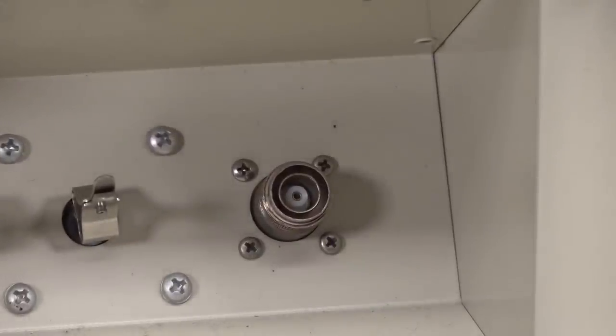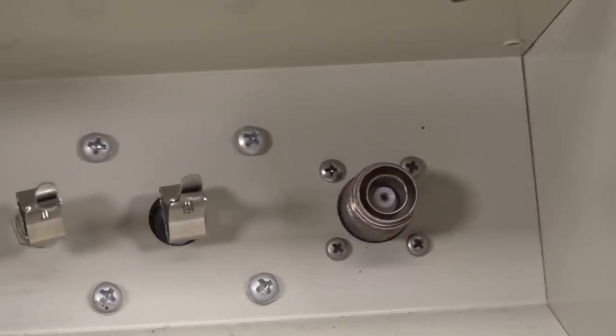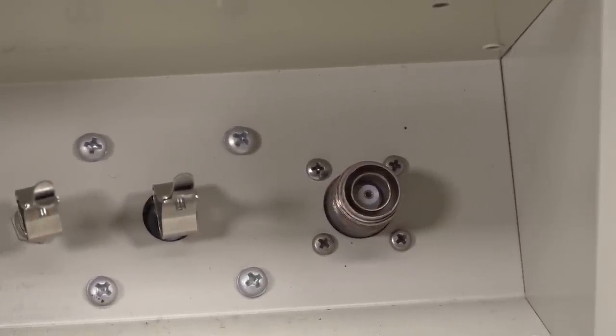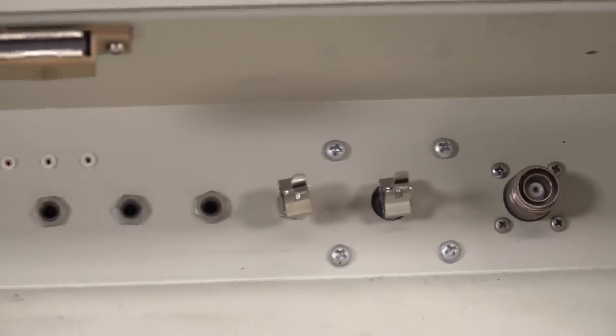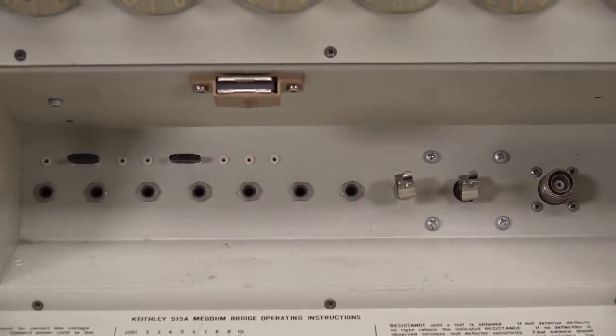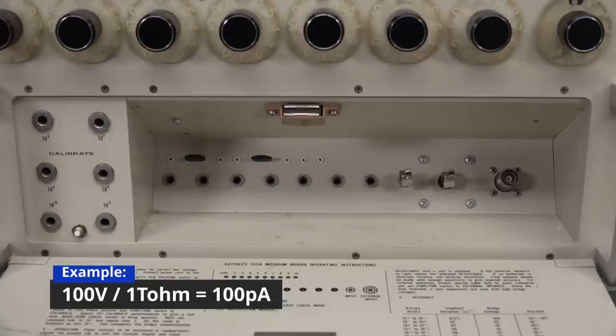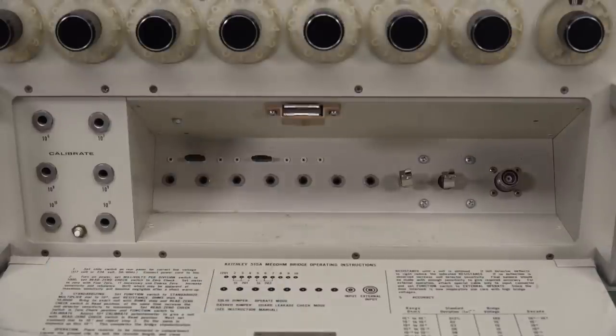And if you've seen my video, I'll link it in. If you haven't seen it, it's really good on the Keithley electrometer and how triaxial connectors work and how the art of measuring extremely low currents works. And that's what you need for something like this. You really need the shielded box triaxial connectors, which have ground and guard connections in there as well. Because when you're dealing with extremely large resistors like gigaohms and teraohms, then you need a really properly shielded and properly designed test fixture. And this has it built in.